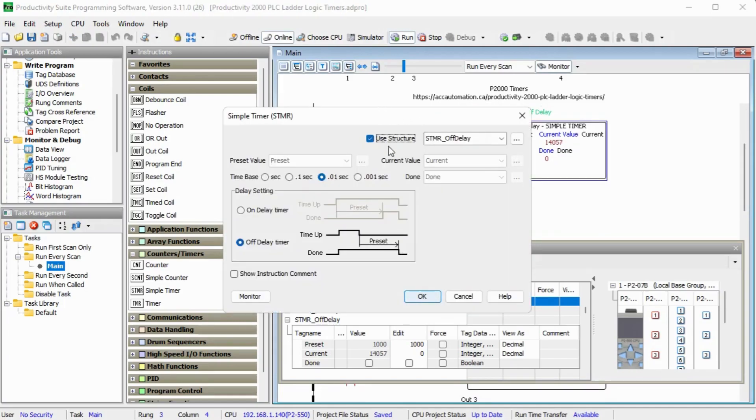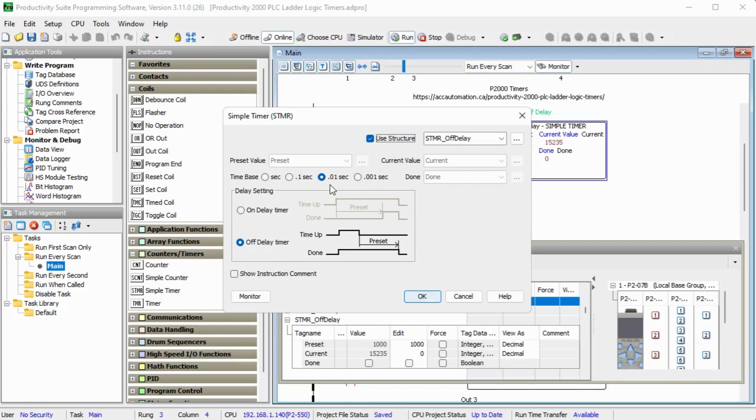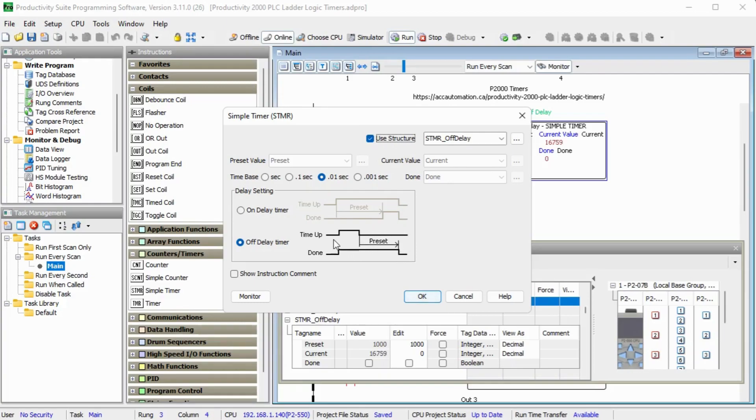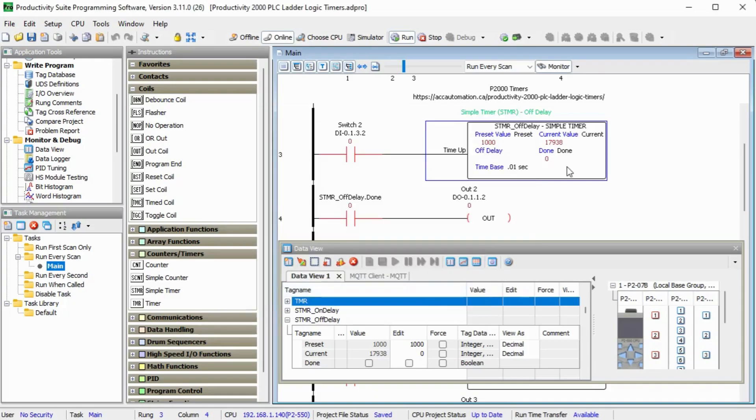So if we call this up, we can see we're again using a structure and our STMR off delay here. And we're again, it's set for 0.01 seconds. We'll set it for 1000 as the preset value. So that means it'll be off for 10 seconds. You can see when I have my input here, it times for the time value of our 10 seconds and it turns off that output. So once my input turns on or my enable turns on, the output turns on. When I turn my enable off, the output then times out for that 10 seconds. So right now we can see that my output is now off.